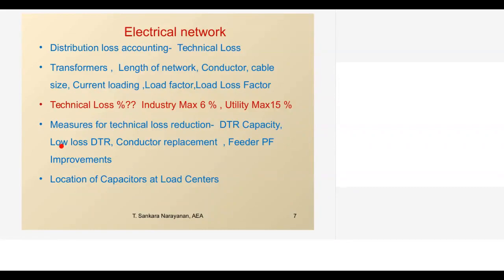Then similarly, some of the utility companies consider a low loss DTR. Today, if you go by the BEE star rating, transformers are given a star rating based on the loss at 50% load and loss at 100% load. So low loss DTR, because a distribution company has a huge number of distribution transformers. Even a small state can have 30,000, 40,000 transformers. So if so many transformers are there, one can invest in the distribution transformer. When we say investment in a distribution company, the investment will not be directly from the distribution company. There are certain schemes they have to consider because the investment required for replacement is high.